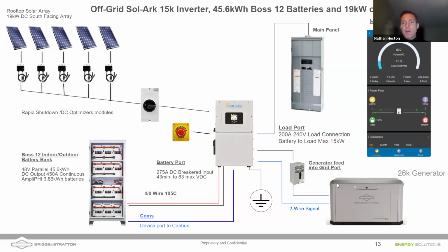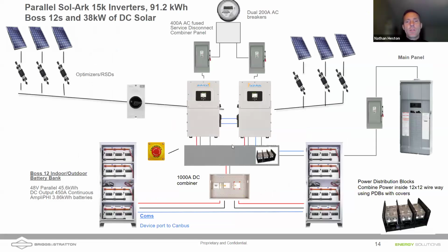We're showing also a generator integrated. So this is an example of a hybrid system. If we could feed this into the grid port of the inverter if we were using a transfer switch, or we could feed this into the generator port of an inverter. Here's an overall larger system. I'm showing here a larger system where we've got 2 BOSS 12 cabinets there, going through a DC combiner. Anytime you parallel inverters, you have to combine into a single battery bank and then power the inverters each individually off that combined battery bank.